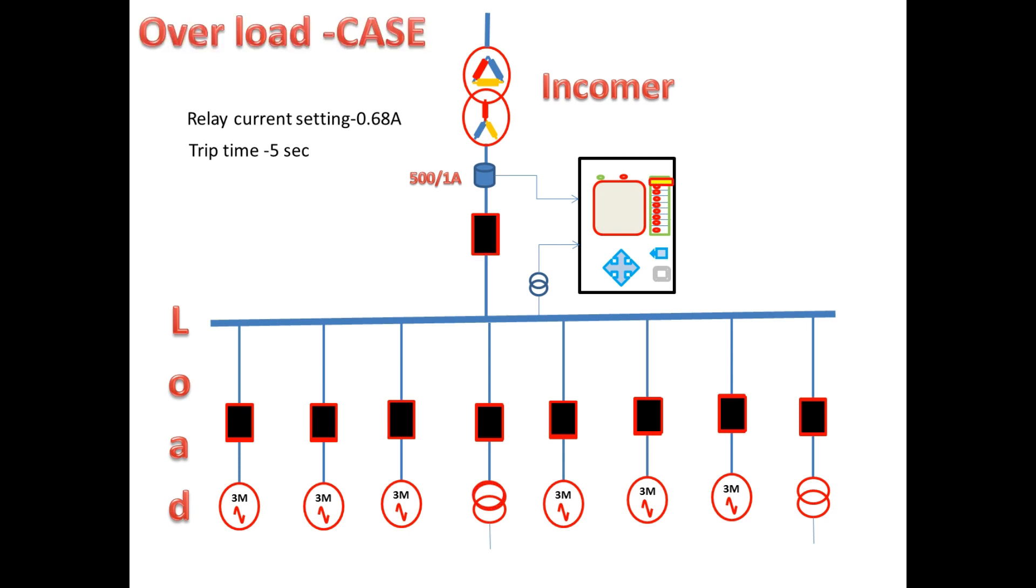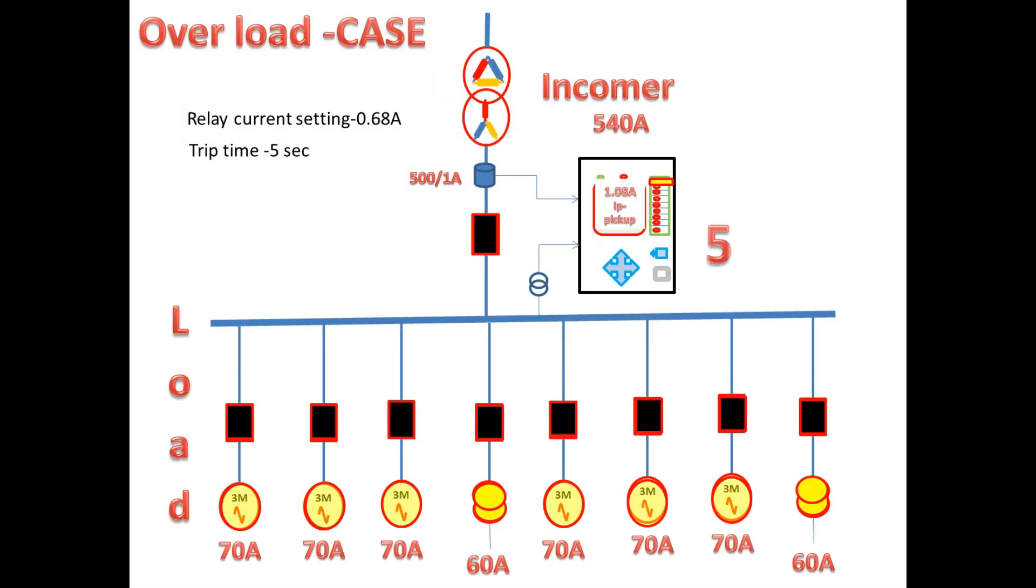Now we go for case 2 if all outgoing get overload. In this case the incomer gets 540A primary and secondary 1.08A according to the CT ratio. So it is greater than the I set. Due to this the relay will start pickup and it will give trip by 5 seconds.